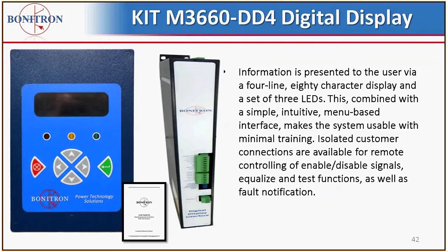As far as the actual display, information is presented to the user via a 4-line, 80-character display and a set of 3 LEDs, combined with a simple menu-based interface. So you can actually use this for some minimal training. You can operate the display without affecting the ride-through unit, depending on which menu you're in. Isolated customer connections are available for remote controlling of enable and disable signals, equalize and test functions, as well as fault notification. So we can send outputs to an Ethernet system, or there are I/O outputs that you can use to either enable the ride-through, depending on your system configuration, or send an enable signal from the ride-through to enable a drive.